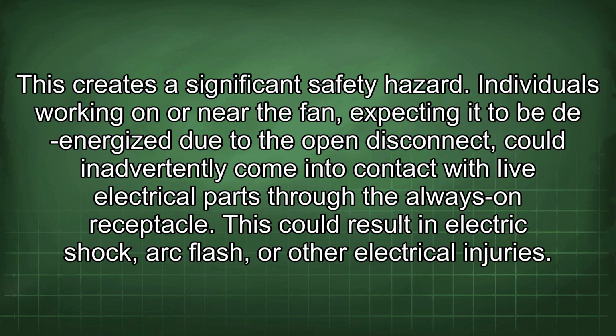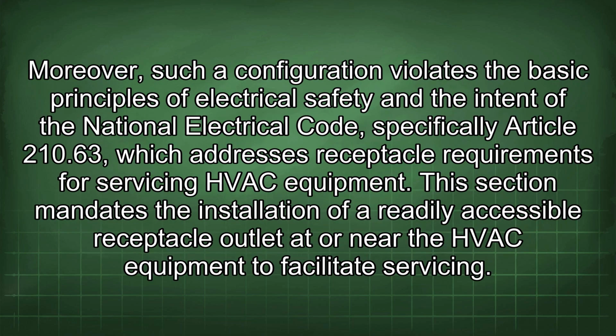This creates a significant safety hazard. Individuals working on or near the fan, expecting it to be de-energized due to the open disconnect, could inadvertently come into contact with live electrical parts through the always-on receptacle. This could result in electric shock, arc flash, or other electrical injuries. Moreover, such a configuration violates the basic principles of electrical safety and the intent of the National Electrical Code, specifically Article 210.63, which addresses receptacle requirements for servicing HVAC equipment.